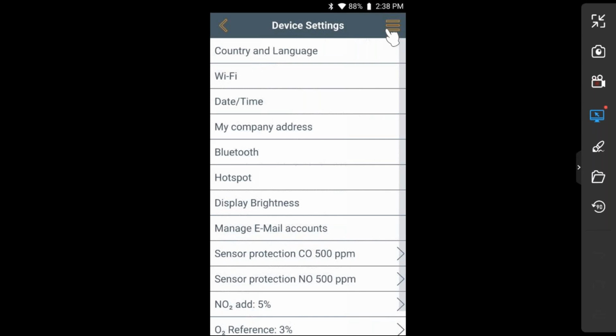And if you're tuning a boiler and you put it into that fuel-rich mixture and you start getting a high concentration of CO and you go over the 4,000 ppm, you could actually damage the sensor and throw it out of calibration. In flue gases, as you know, we should see less than 100 ppm CO. And even though the sensor goes up to 4,000 ppm, we want to shut that instrument off way before it gets over that 4,000 ppm. And usually I set it at 2,000 or so.